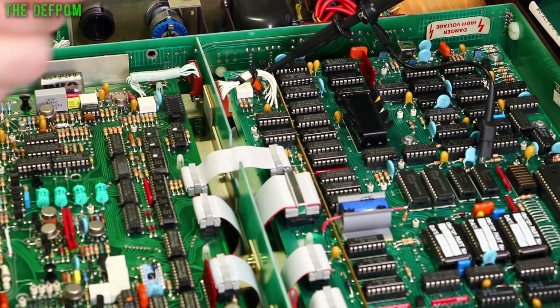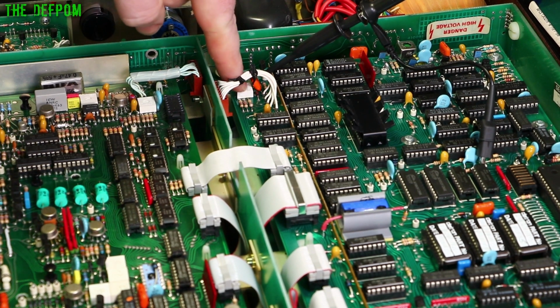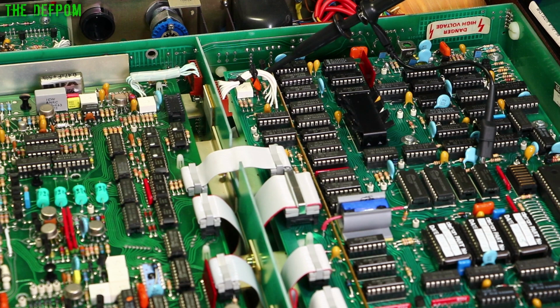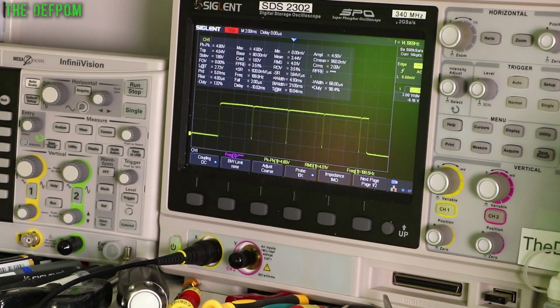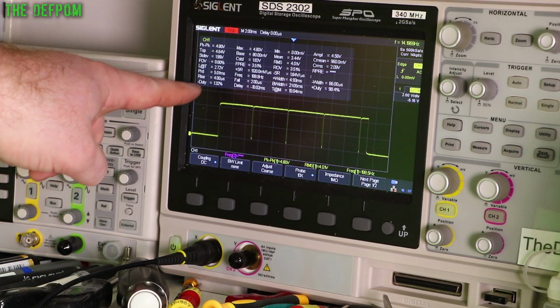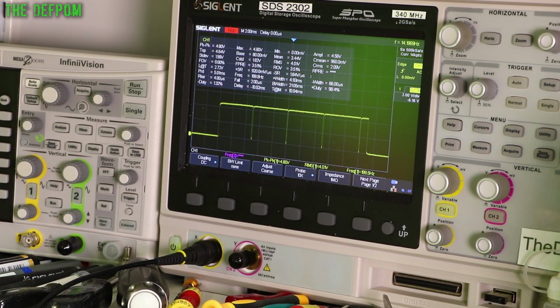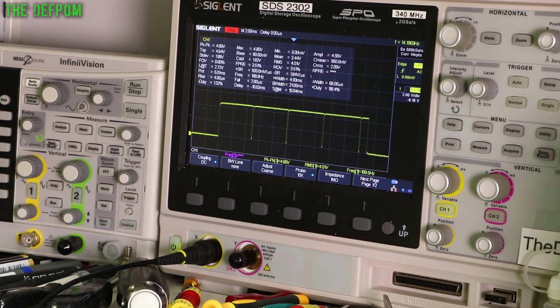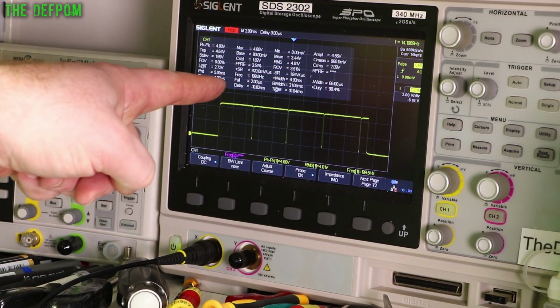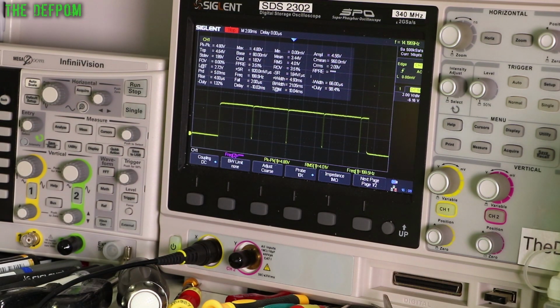To there like that. And I need to adjust R11, which is this trimmer over here, on the oscilloscope once more and adjust that. So measuring at that test point, I'm getting a 5.01 milliseconds delay time, and according to the electronic manual for this machine, that is correct. Now the 1062 has a 5 millisecond pulse time set up, and the 1061 and 1061A, which I'm using the physical manual for, says 6 milliseconds. This is fine. That's exactly what it's supposed to be. So great, we'll move on.